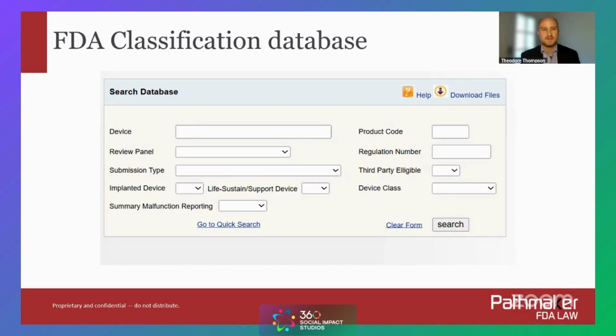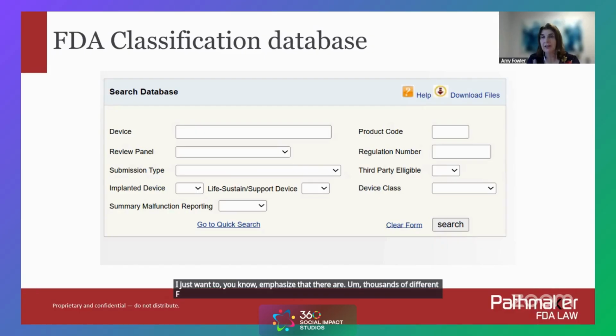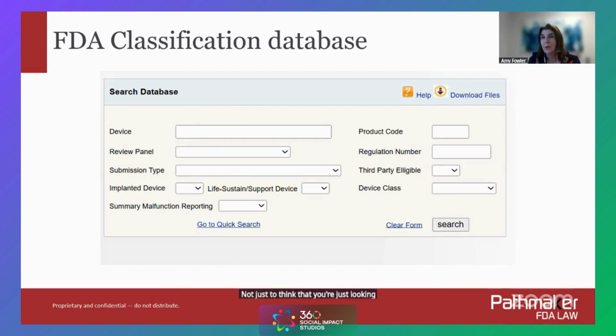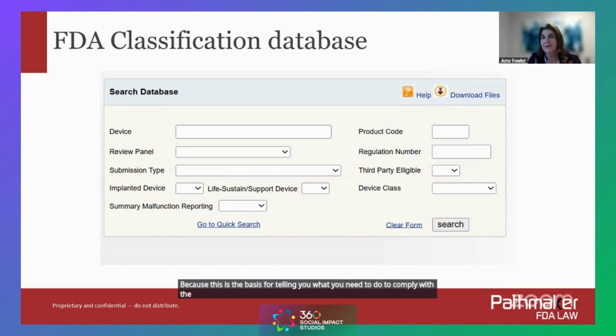Do you have anything that you would like to add in terms of the FDA database, Amy? I just want to emphasize that there are thousands of different FDA classifications. So it's very important not just to think that you're just looking for class 1, class 2, or class 3. You really have to use this database to figure out which specific classification paragraph applies to your product, because this is the basis for telling you what you need to do to comply with the regulations.